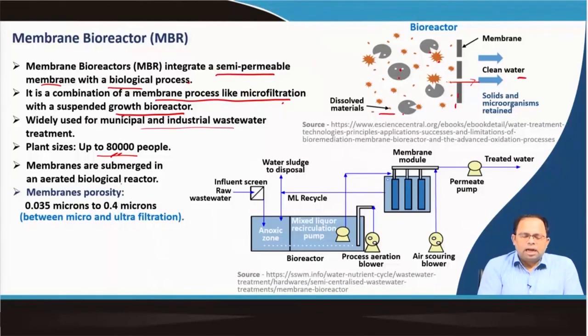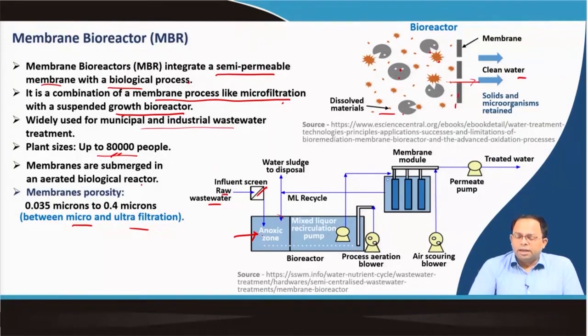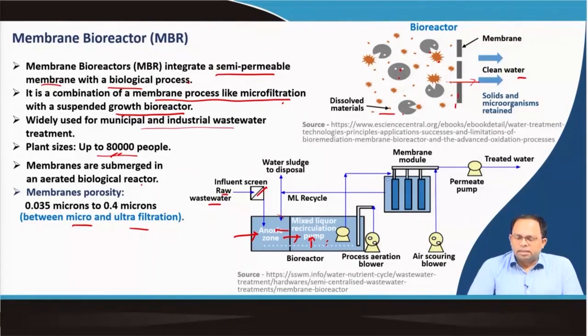Membranes are submerged in an aerated biological reactor — sometimes attached to the bioreactor, sometimes separated. Membrane porosity is around 0.035 to 0.4 microns, which is between micro and ultra filtration. In this image, raw water comes in through a screen into the first anoxic zone — no aeration, so denitrification takes place — then it moves to the next zone with a mixed liquor recirculation pump, where existing sludge is mixed with incoming wastewater. An aeration blower also introduces air into the system.